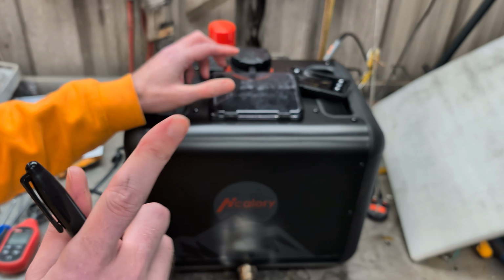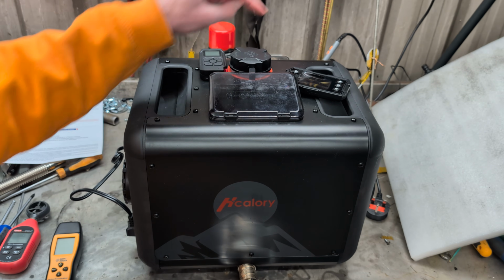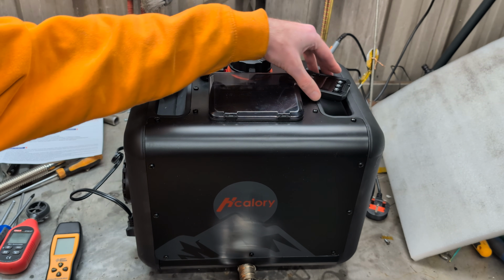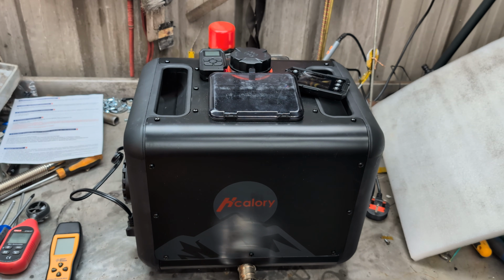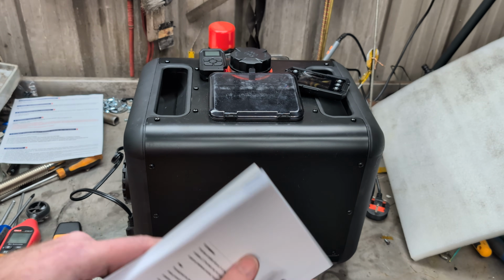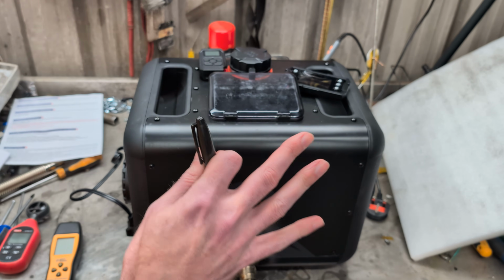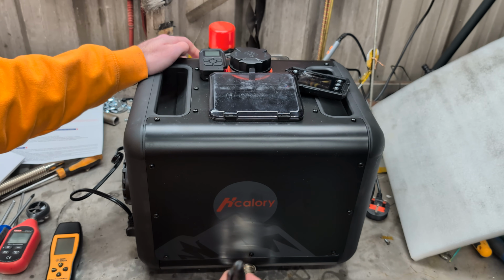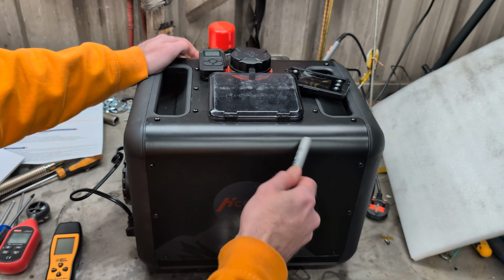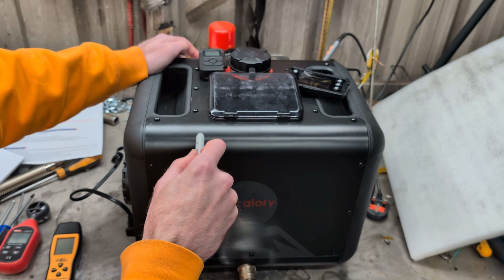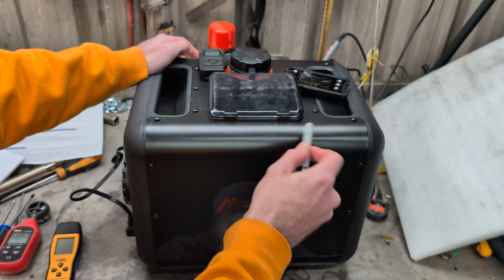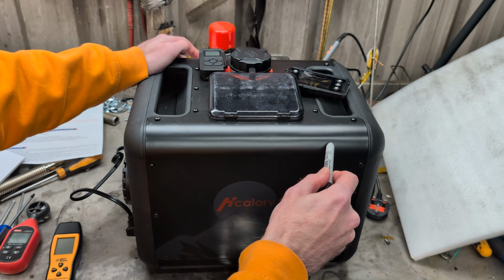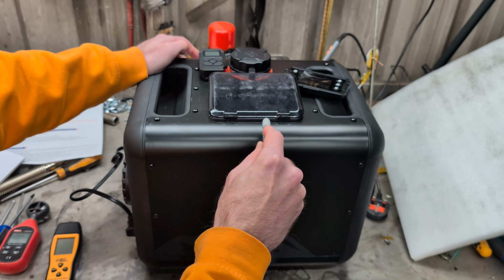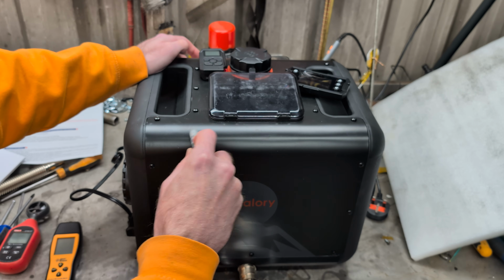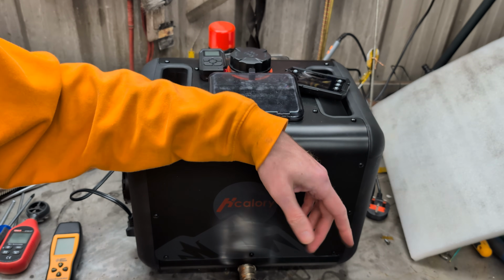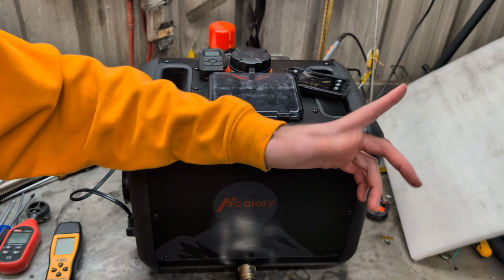A very worthy note is you can tune it. There is a setting in the settings, and in the manual, where you can enter the password and adjust the fueling parameters. You can't adjust the air speed, it just gives you a 1 to 10 option for the 10 power levels, but you can set the fueling on each of the 10 power levels, which is interesting. It's not just a minimum and a maximum, it lets you set a fuel quantity for each power level, so you can actually tune it for every single one of the power levels, which is an interesting way of doing it, I thought.